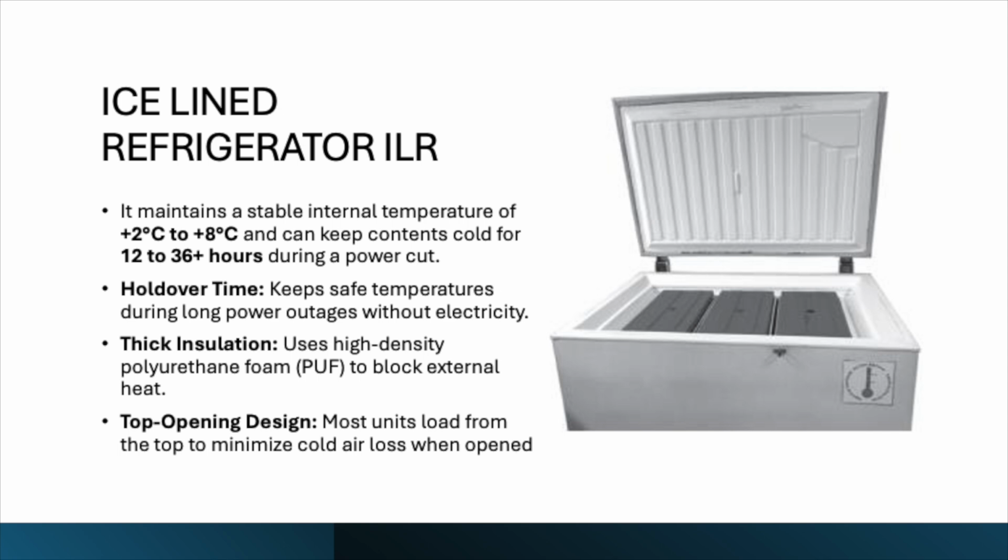Now, let us move to the ice lined refrigerator or ILR. It maintains a stable internal temperature of plus 2 to plus 8 degrees Celsius and can keep its contents cold for 12 to over 36 hours during a power cut. This performance comes from three features.